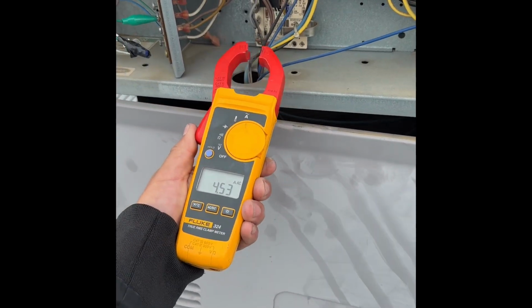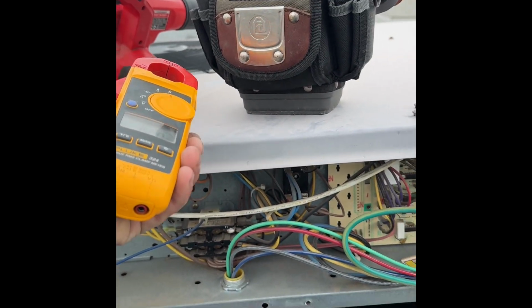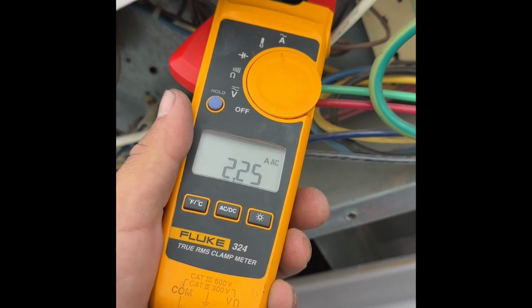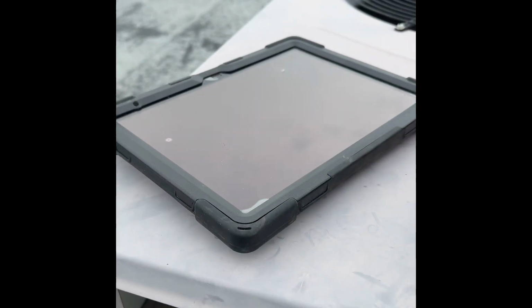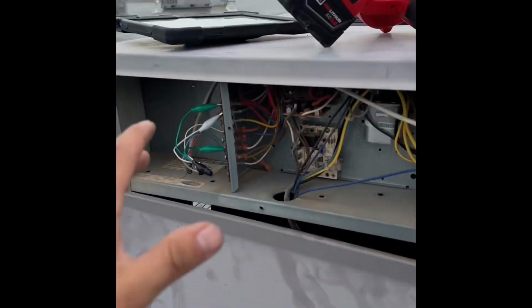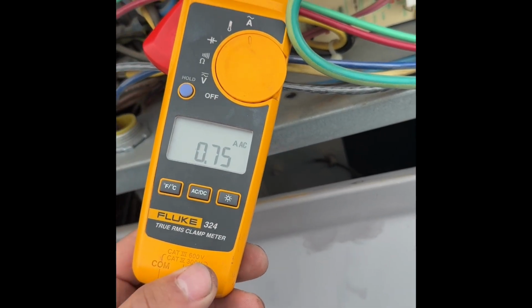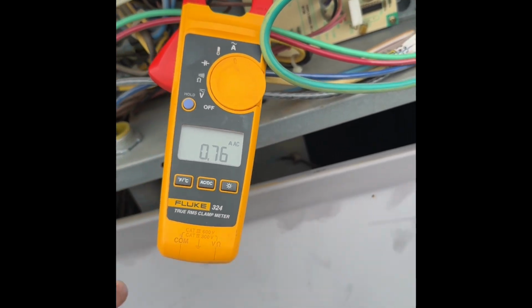Now we're gonna move over to our condenser motor and our evaporator motor, or in other words, outdoor fan motor and the blower. So let's find our wire for the blower. It's gonna be this relay right here. It's common. Double check, make sure it makes sense. We're at 2.25 for our blower, so that's good. And again, when you're taking these readings, you're going to be documenting it on your ServiceTitan app for the company that you work for or whatever. So this is all tangible information that needs to be documented and recorded. I already did it for all the systems. This is just for us. So now we're at the outdoor fan motor, 0.76. Double verify our name tag, what we need. What's the target?